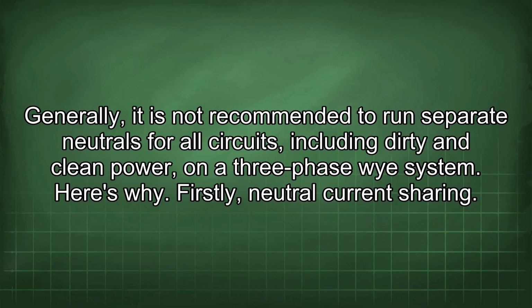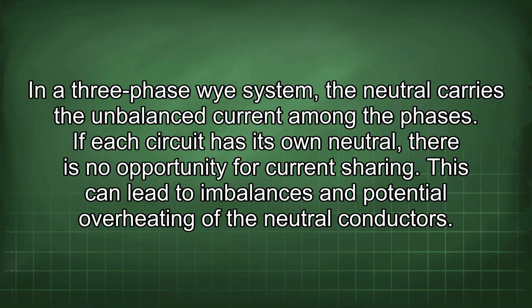Generally, it is not recommended to run separate neutrals for all circuits, including dirty and clean power, on a three-phase Y system. Here's why. Firstly, neutral current sharing. In a three-phase Y system, the neutral carries the unbalanced current among the phases. If each circuit has its own neutral, there is no opportunity for current sharing. This can lead to imbalances and potential overheating of the neutral conductors.